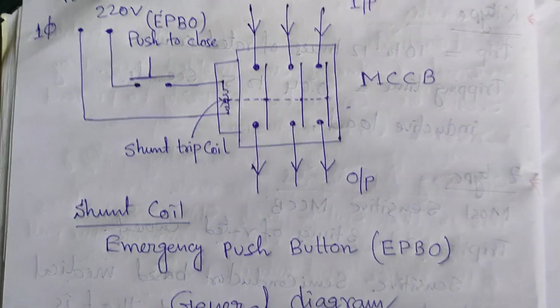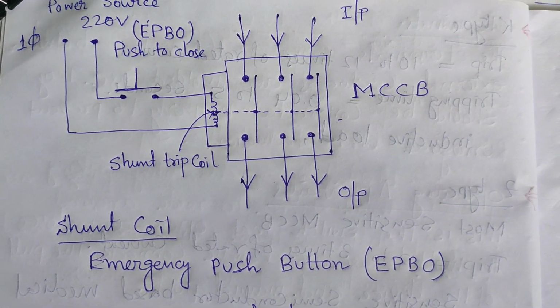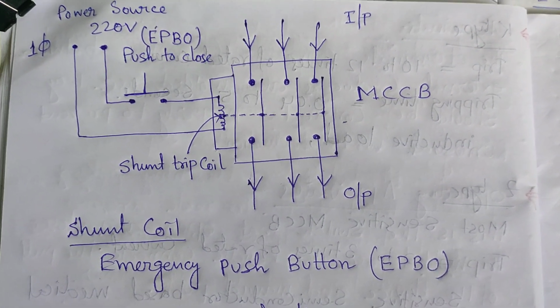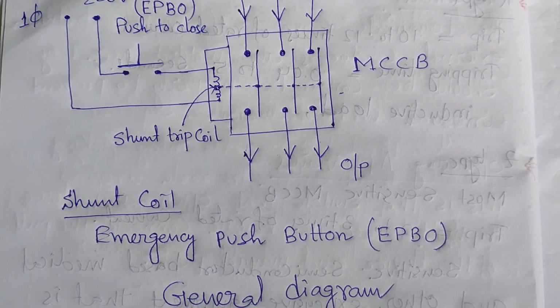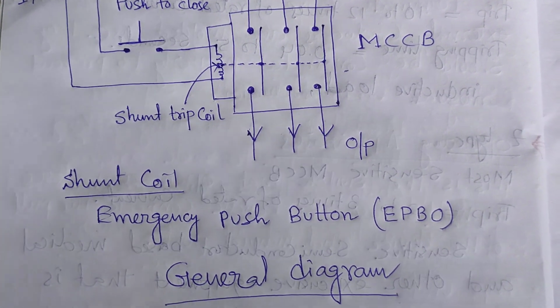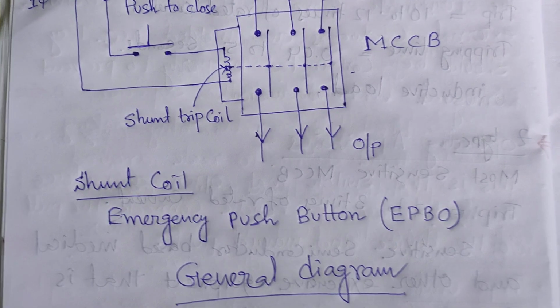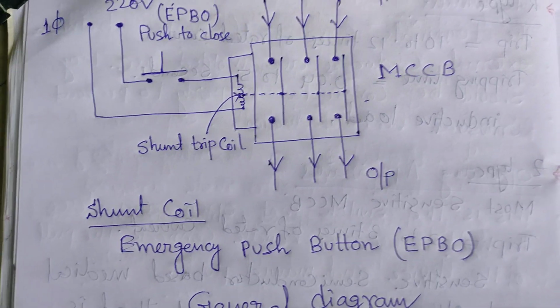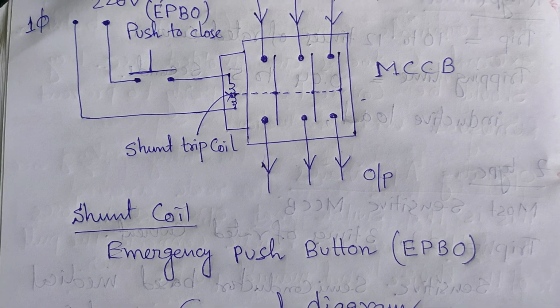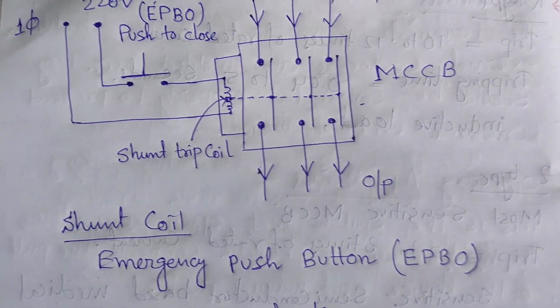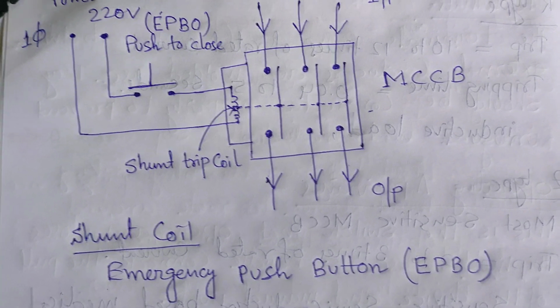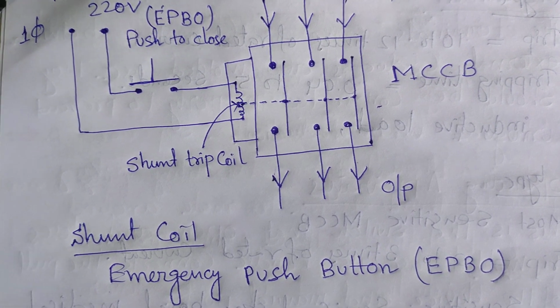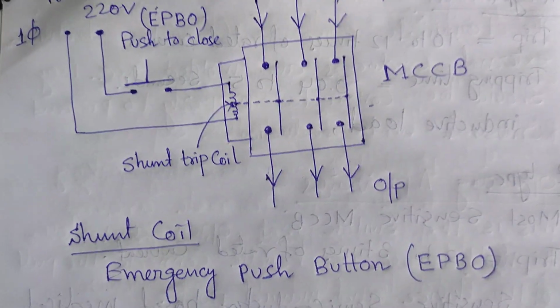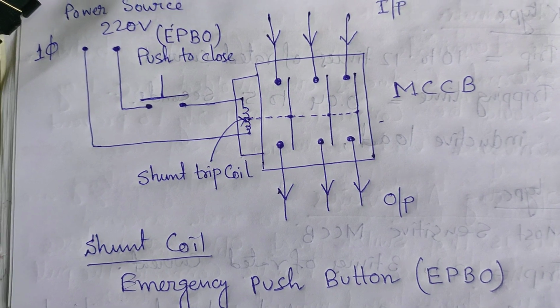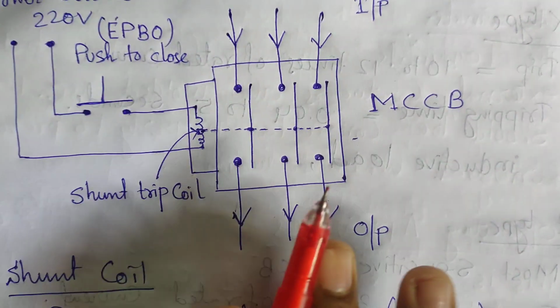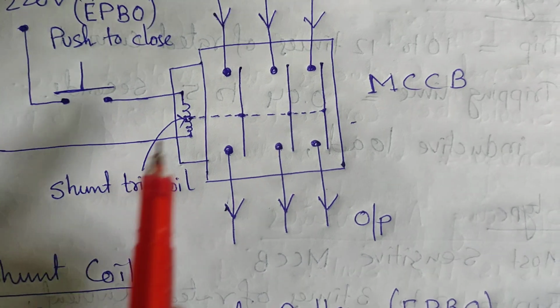I have drawn a simple circuit for your better understanding, because inside the MCCB, if you open the upper molded case, two pockets are there. In one pocket you can connect the shunt coil, and in the other pocket an NO/NC contact. What is the function of the NO/NC contact? It is connected to the DC source, and the shunt coil is connected to the AC source. It is single phase. We are just drawing a picture of the shunt coil.